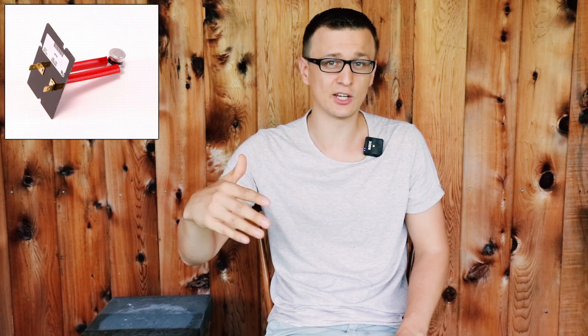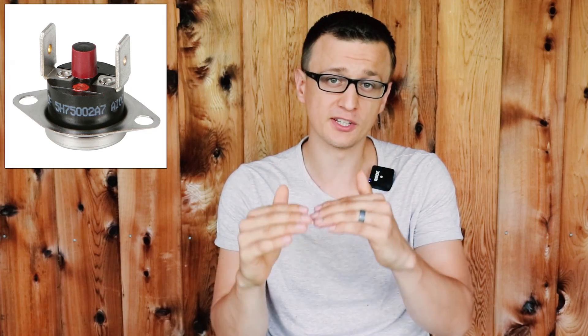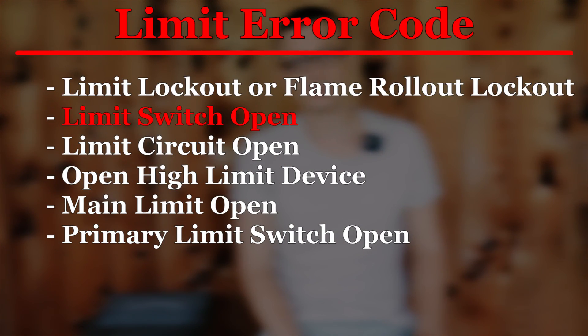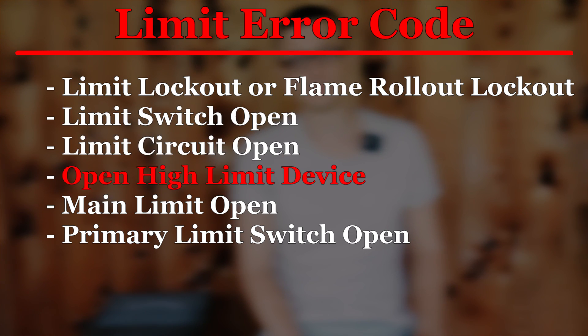Moving on to the next error code: limit switch or rollout switch open. Even though these are two different safety switches on a furnace, on most furnaces both of them are grouped together under the same error code. The purpose of the high limit is to shut the furnace off if the furnace is overheating or getting too hot. The purpose of the flame rollout switch is to shut the furnace off if for some reason your combustion fumes are coming back out of the heat exchanger and back into the burner box. Here are a few examples of what a limit error code would look like: limit lockout or flame rollout lockout, limit switch open, limit circuit open, open high limit device, main limit open, primary limit switch open. Even though the wording is all different, it's all talking about the same thing — usually it's the high limit switch, but on some furnaces limit lockout may refer to either the high limit or the flame rollout.